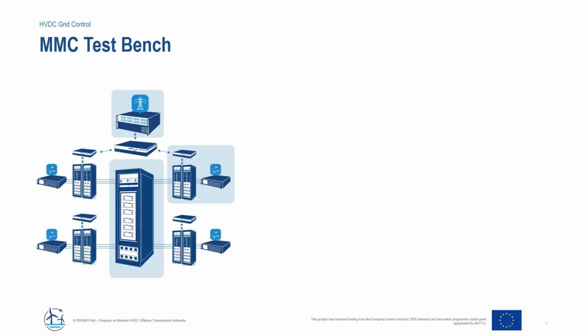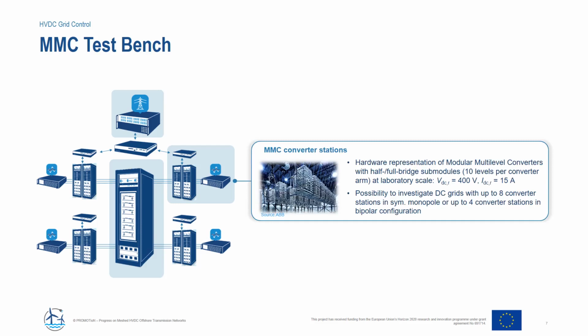So for the purpose of these demonstrations, we built a small-scale HVDC grid demonstrator at the RWTH Aachen University over the course of the project, and this is called MMC Test Bench. At the core of the test bench, there are 8 laboratory-scaled modular multi-level converters with a power rating of 6 kilowatts and a nominal voltage of 400 volts. The MMCs are built similarly to HVDC grid converters. However, instead of having several hundred submodules, they only comprise 10 submodules per arm, which is completely sufficient for our test levels, however.